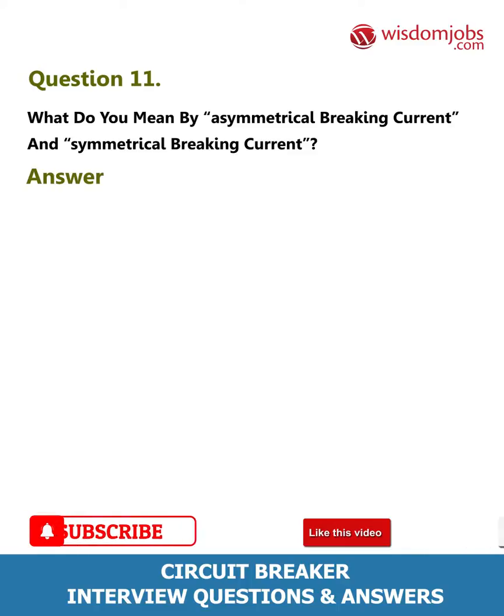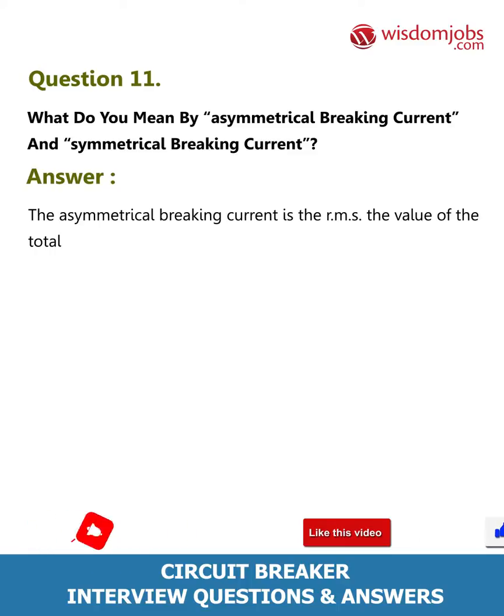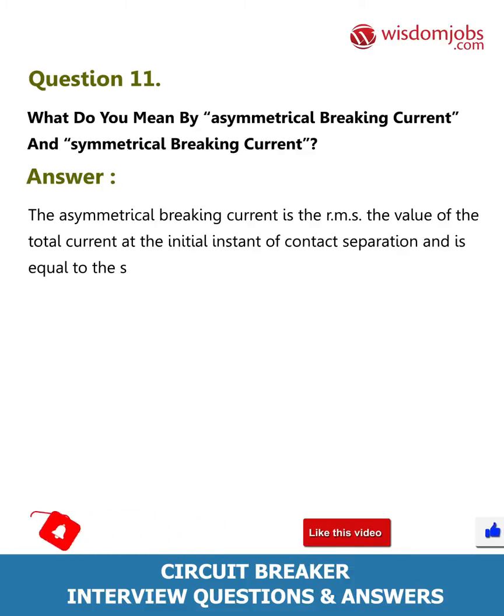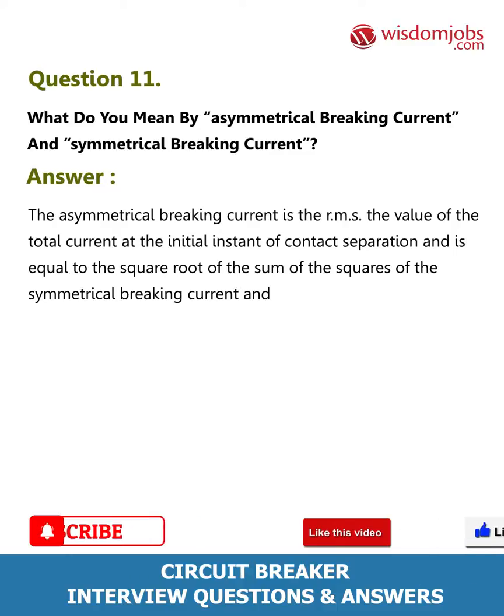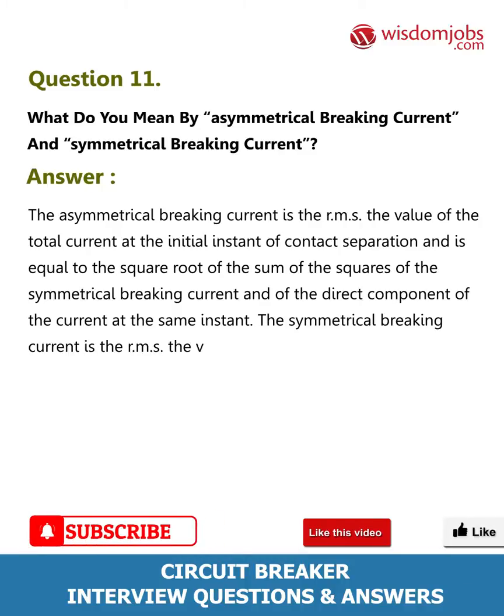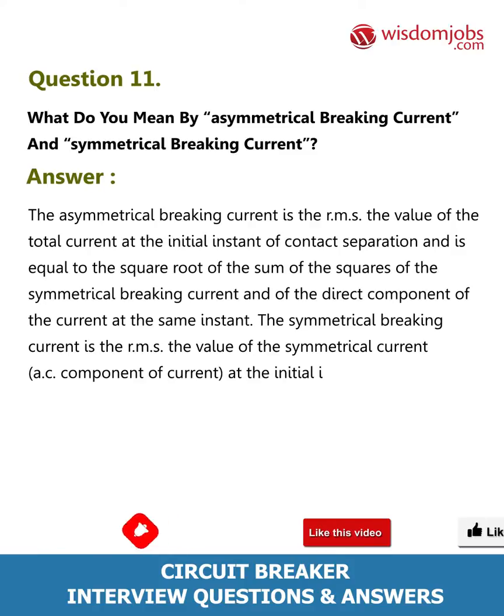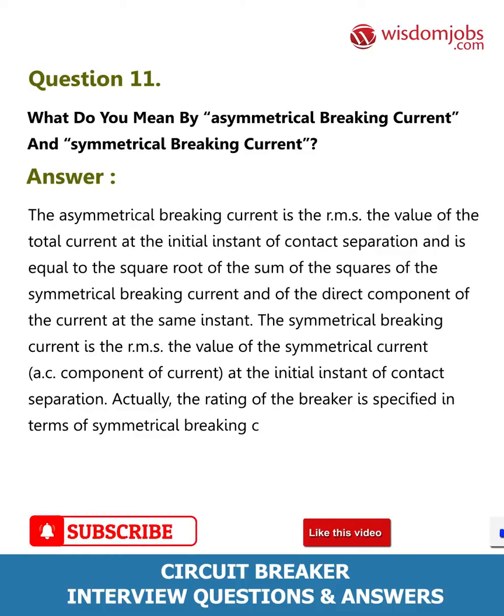Answer: The asymmetrical breaking current is the RMS value of the total current at the initial instant of contact separation, and is equal to the square root of the sum of the squares of the symmetrical breaking current and the direct component of the current at the same instant. The symmetrical breaking current is the RMS value of the AC component of current at the initial instant of contact separation. The rating of the breaker is specified in terms of symmetrical breaking current and voltage.